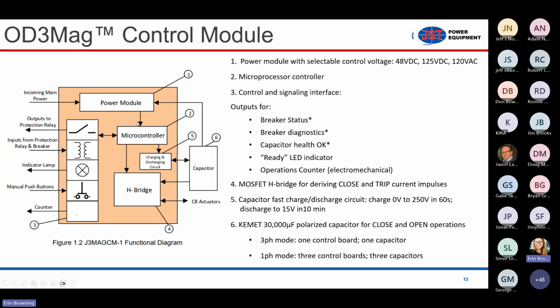And so once the control board receives a trip or a close command from the customer's Schweitzer relay, for example, because it sensed an overcurrent situation, that digital input to the control board is going to allow the capacitor to discharge voltage through the control board through a MOSFET bridge, and that's what dictates the polarity of the voltage that's going to the actuator, and that's what dictates whether it moves up or down or open and closed.